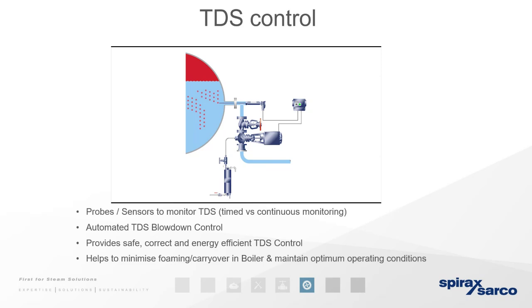Any other questions, Anthony? Yes, there's another question: what is the limit for the TDS value? So it depends on the boiler manufacturer. I think we use is it a value of 2,500? Is that what we state on our controllers? Maybe Cornelius can clarify on that one. We use 3,000 to 3,500. Generally speaking, it's a fairly decent balance.